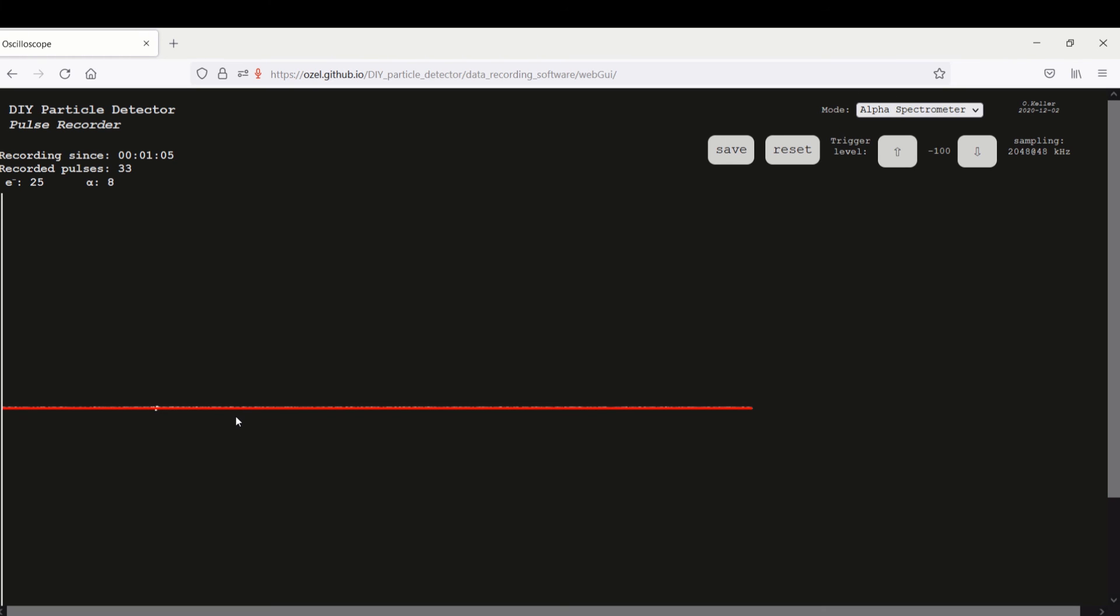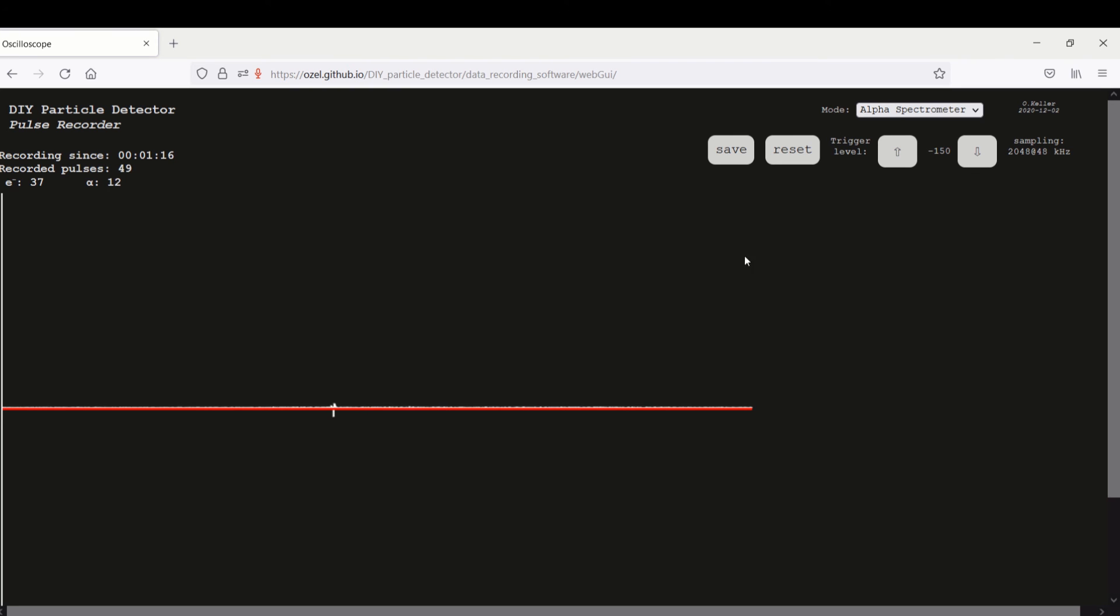And it's counting now the pulses. If it's counting too much noise or whatever, we can lower the trigger level. Now we have a pretty high one and it's counting a lot of pulses but I think 150, 100 is fine.